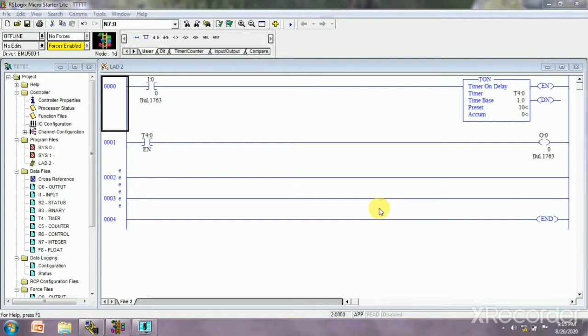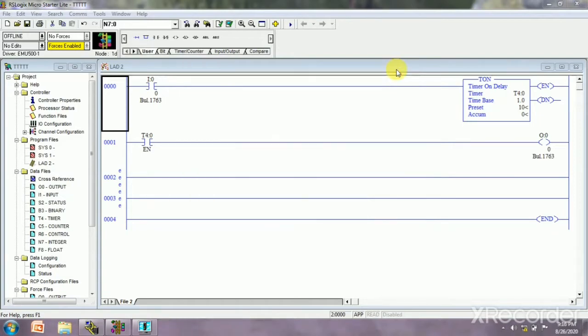First is T-ON, that is a Timer On Delay — it means when we start the output, it takes some time for starting a motor. T-OFF means when we turn off the switch, then after some time the output will get off. RTO is related to T-ON, but the difference is that with T-ON and T-OFF the accumulator gets reset automatically when we remove the toggle bit, whereas with RTO the accumulator will not reset automatically — we have to reset it manually using the reset button.